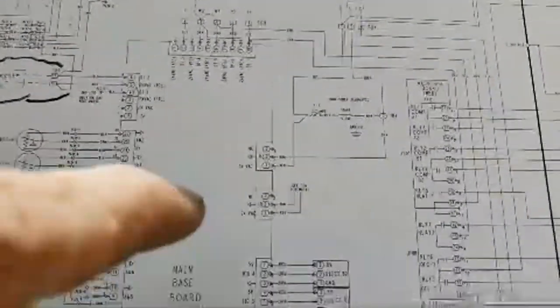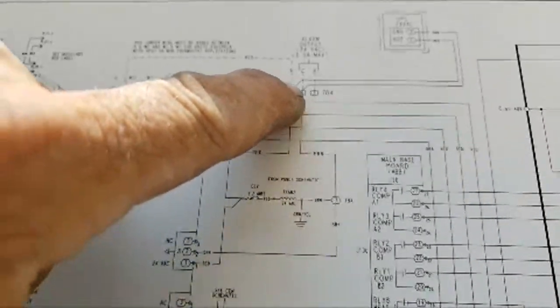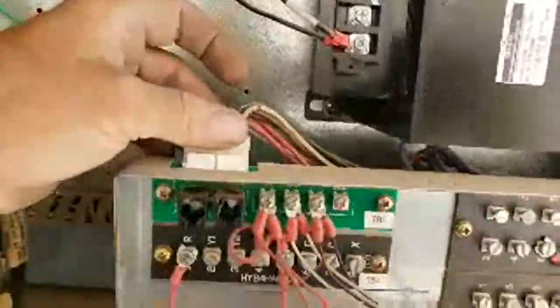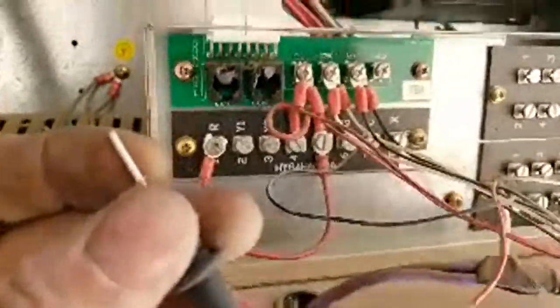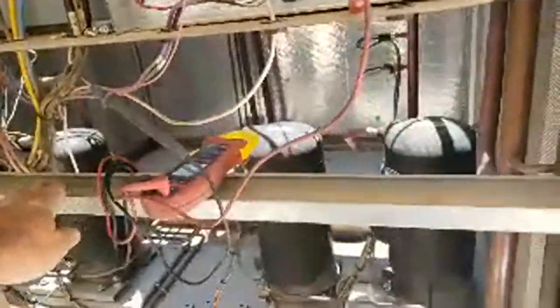Where else does it go? Well, it goes up, red goes here. It goes to the UPC, which is a unitary protocol converter somewhere. And it also goes down to these relay contacts, J10A. But also somehow it comes down to here. I unplugged this, isolated, still did it. But then when I unplugged this terminal here, I isolated it. Stopped tripping. Thank God, it's probably in this cable somewhere.